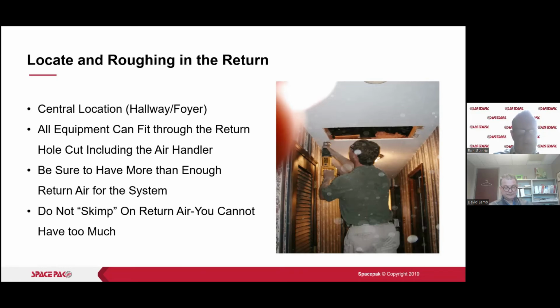All right. As I mentioned earlier, the equipment can fit through the return, and the filter grill would go back in its place. Make sure that there is enough room underneath the doors for return to go into that common area that we're returning from. If you get the return down and you have adequate return, you'll save yourself a lot of problems. You can actually feel when you pull the filter out, you can almost feel the difference with the air flowing through the unit. You're really holding it back by having a pleated filter in there or inadequate return in the system.